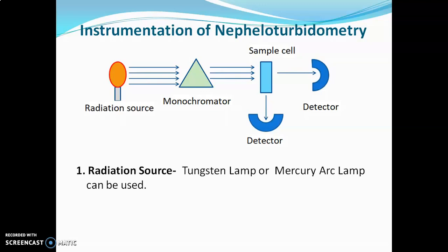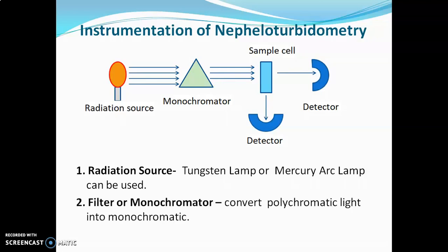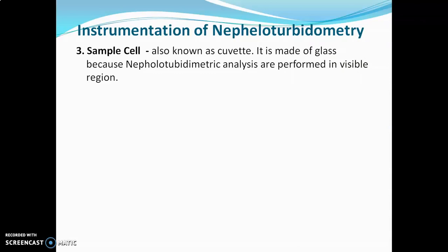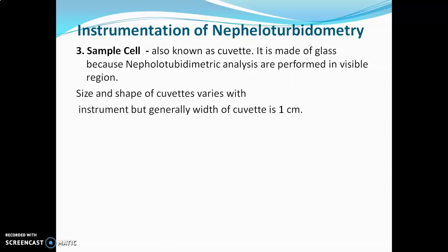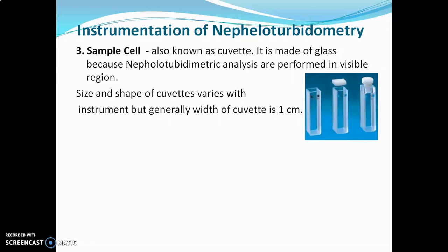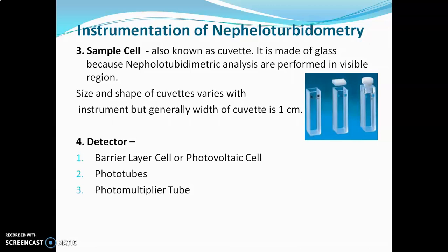The radiation source used is a tungsten lamp or mercury lamp. A monochromator and filter are used to convert polychromatic light into monochromatic light. The sample cell, also known as a cuvette, is made up of glass in nephelo-turbidometry because the analysis is performed in the visible region. The width of the cuvette is generally 1 cm. Detectors used are barrier layer cells, photovoltaic cells, phototubes, or photomultiplier tubes. These components are also explained in the instrumentation of UV-visible spectroscopy.